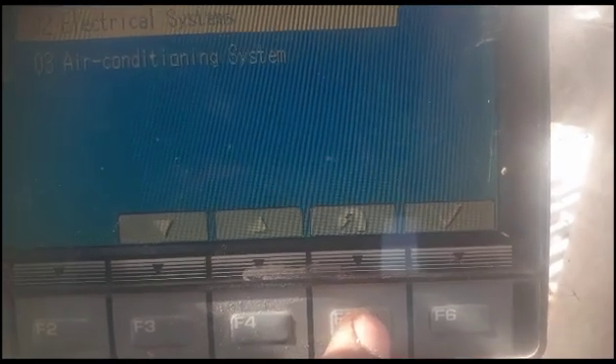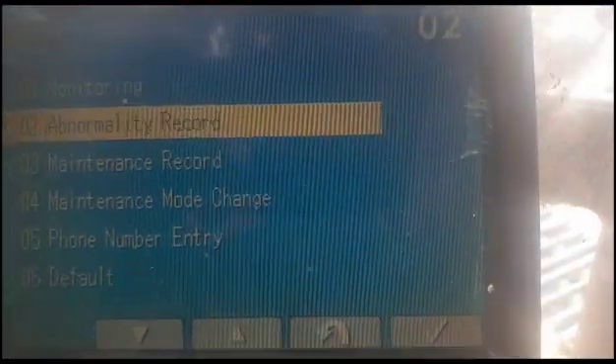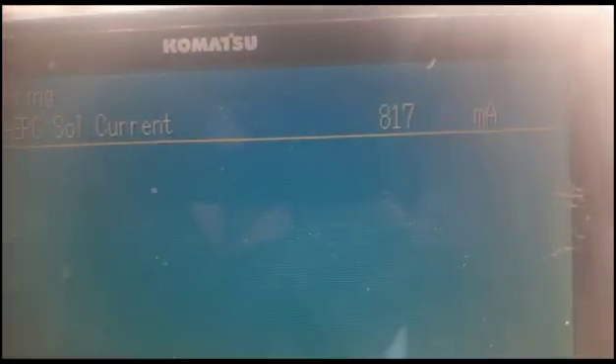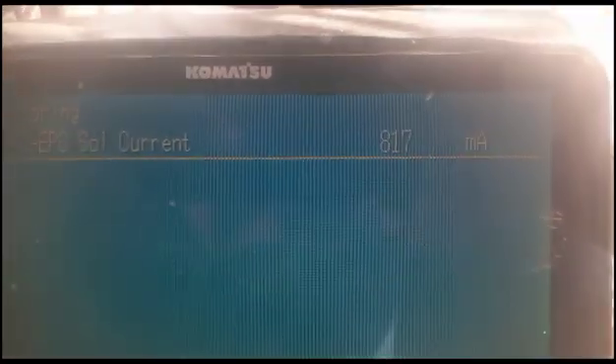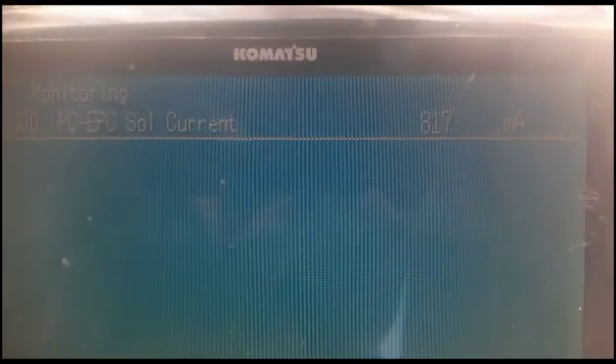My code is finished and my problem is resolved. I also check the current — going to the monitoring system, scrolling to PC EPC solenoid current. I press it for a couple of seconds and now you can see: before, the current was 5 milliamps; now it is 800 milliamps. Current is passing, so my fault has gone and the solenoid is getting current. My machine is okay.